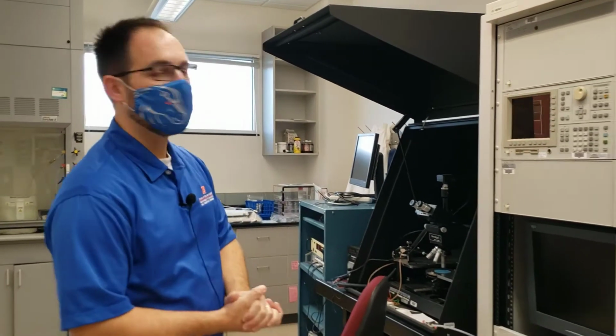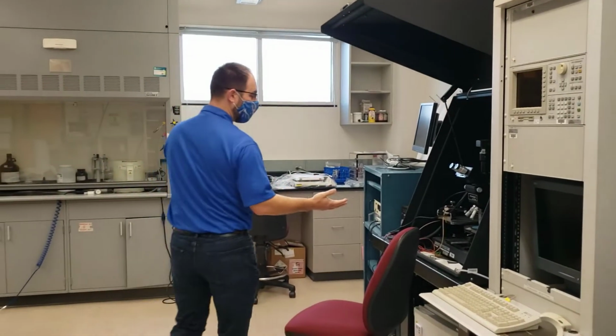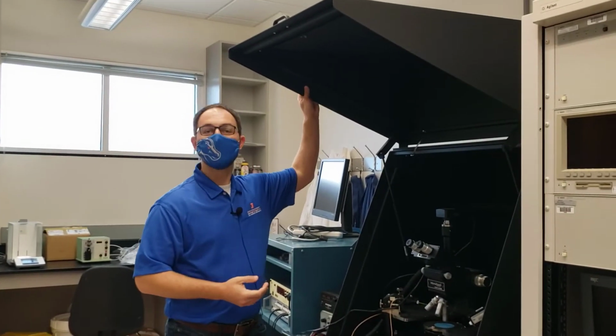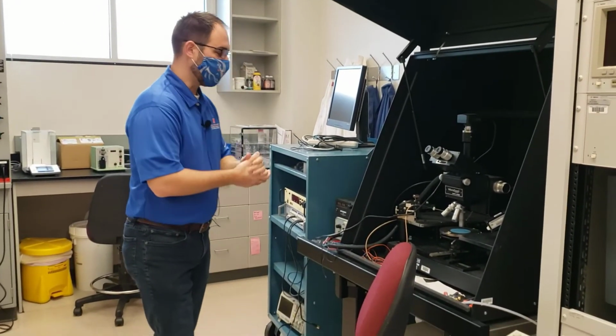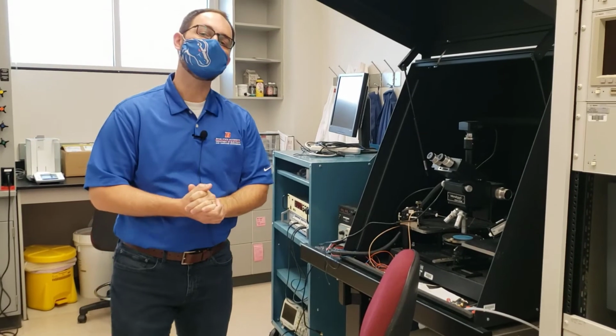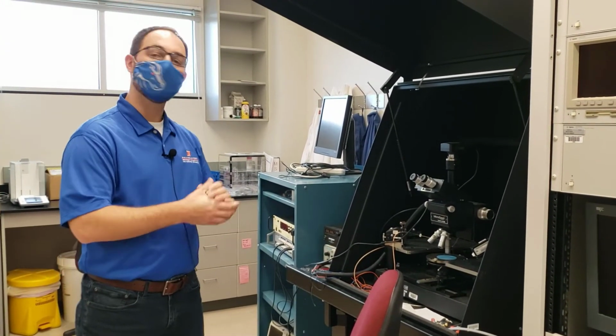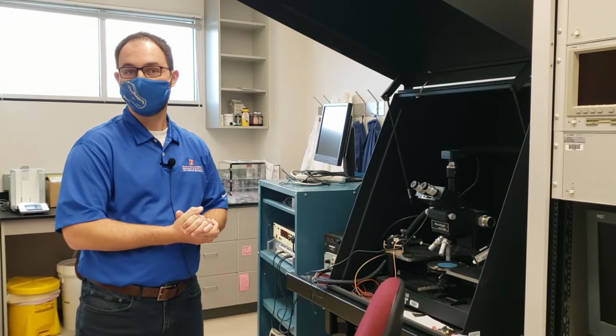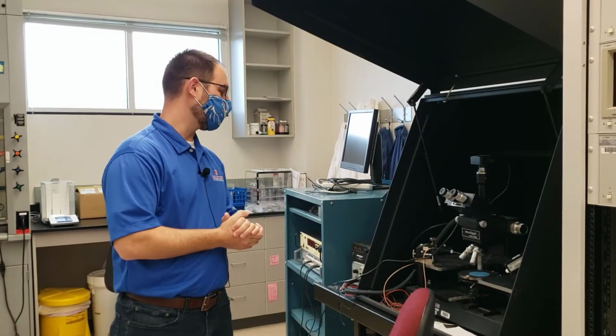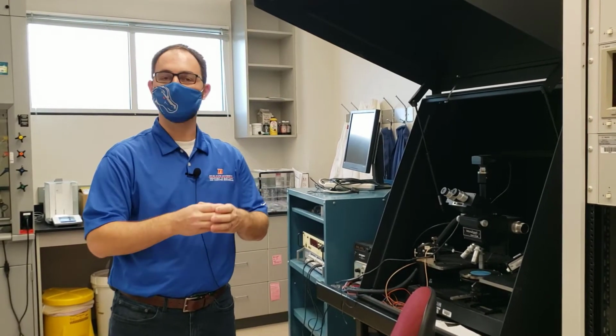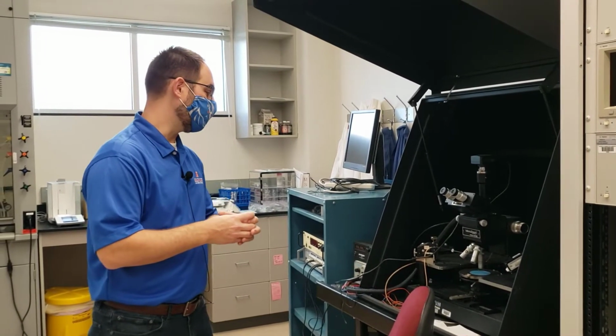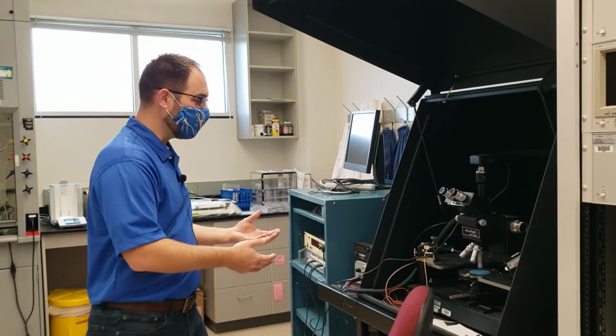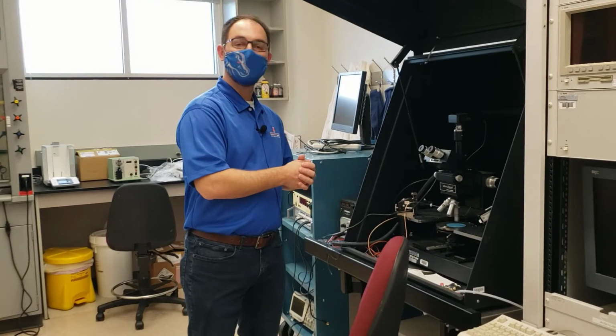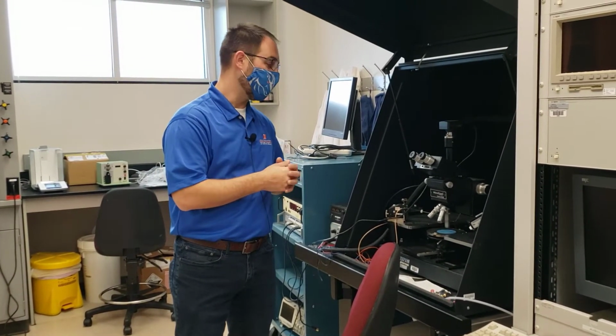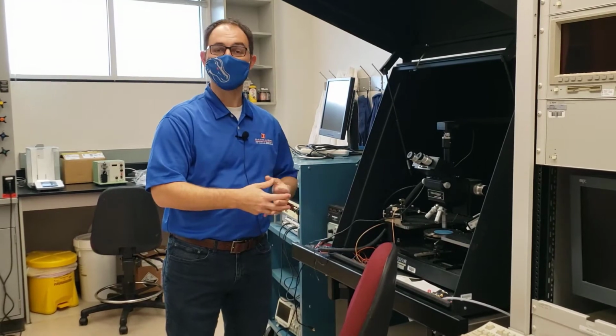So this rack also connects to another custom probe station over here, which is primarily used for electrophysiology, also contained inside of a black box Faraday cage, with a heated stage that will warm samples up to 37 C, biological temperatures, and micropipette positioners as well as microprobe positioners. What we'll typically do is create a reservoir with a salt solution fluid inside, where we can culture neuron cells, bring them here, put them on the stage, and measure the electrical properties of the cells themselves, and put those on neural interfaces and measure the properties of the neural interface also.